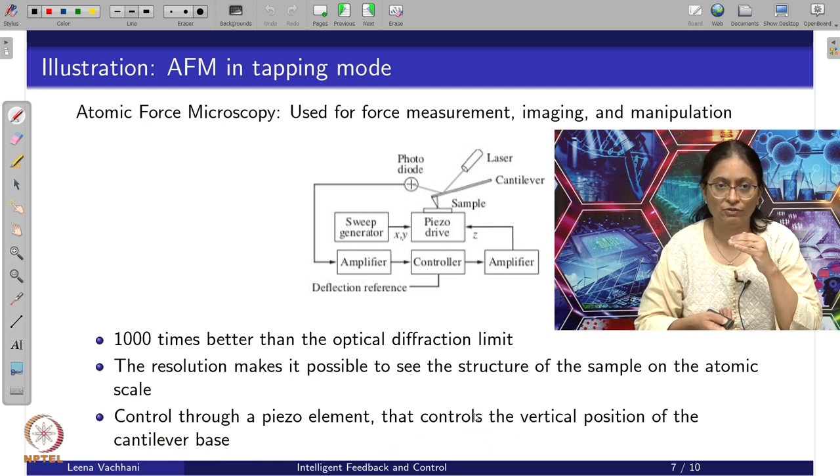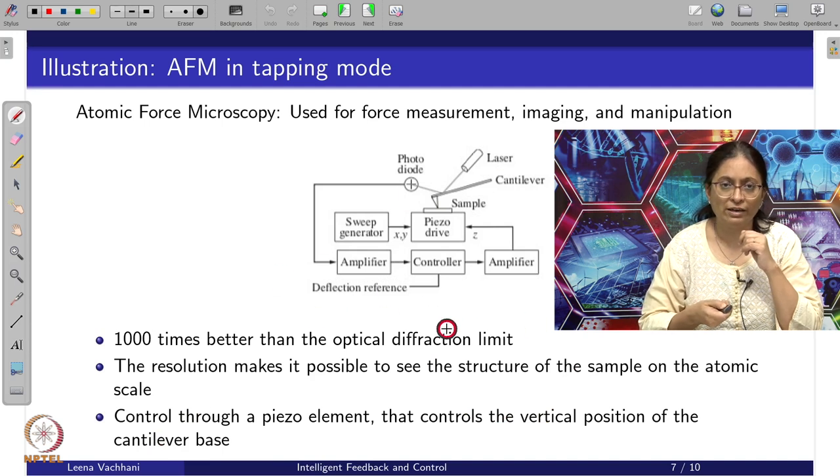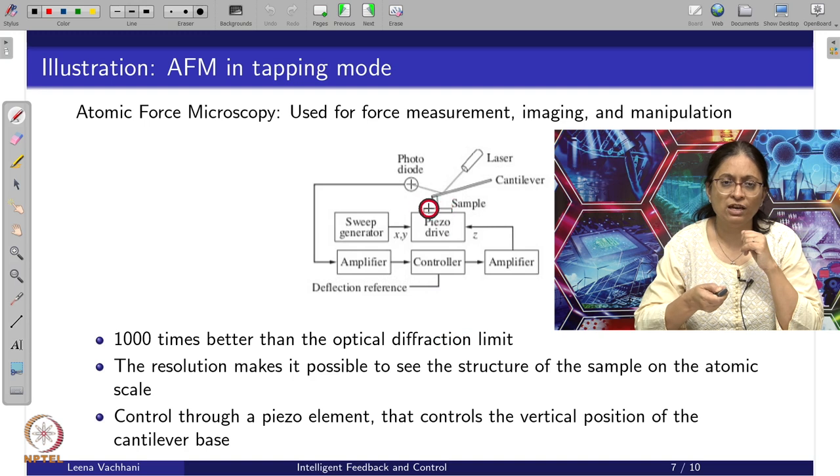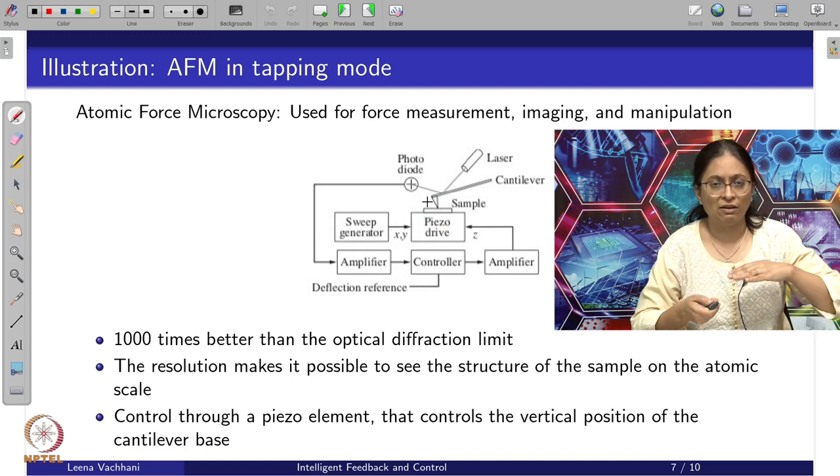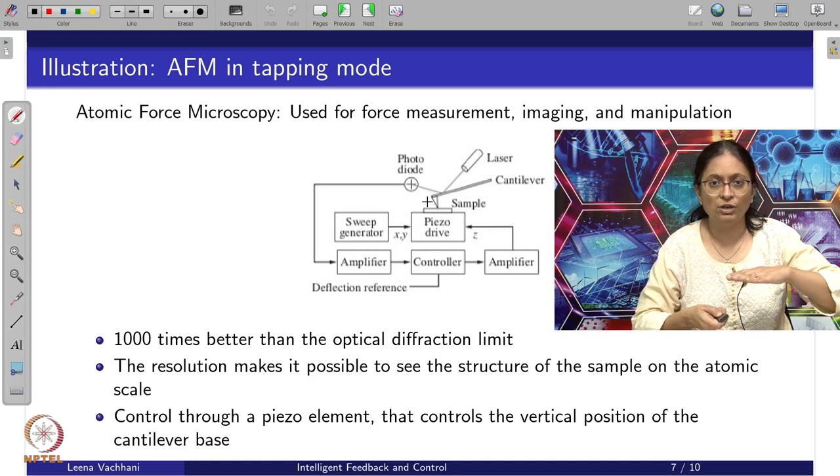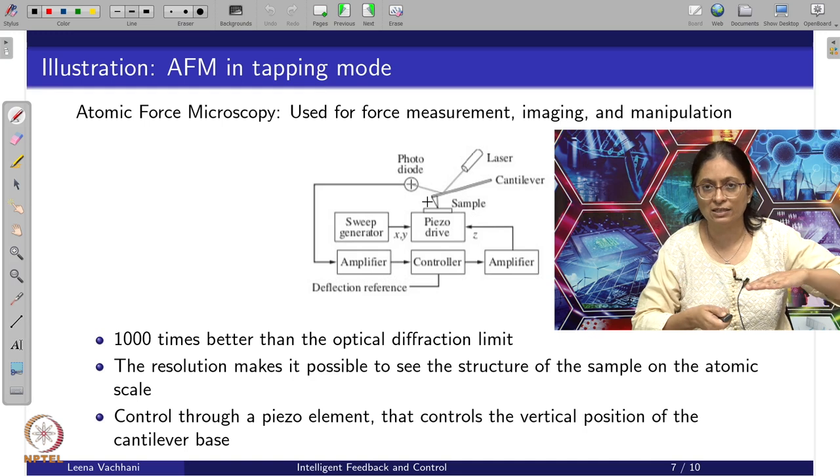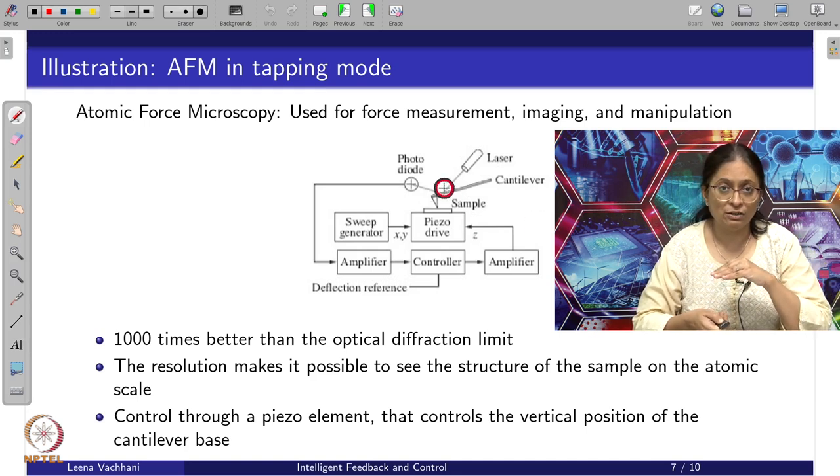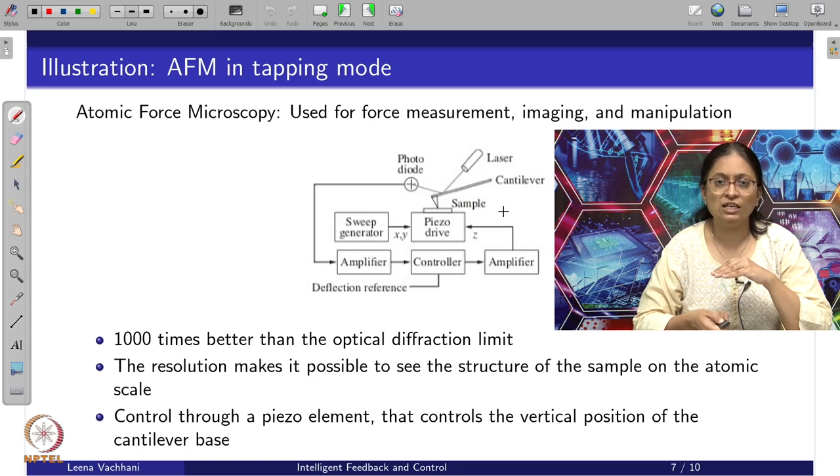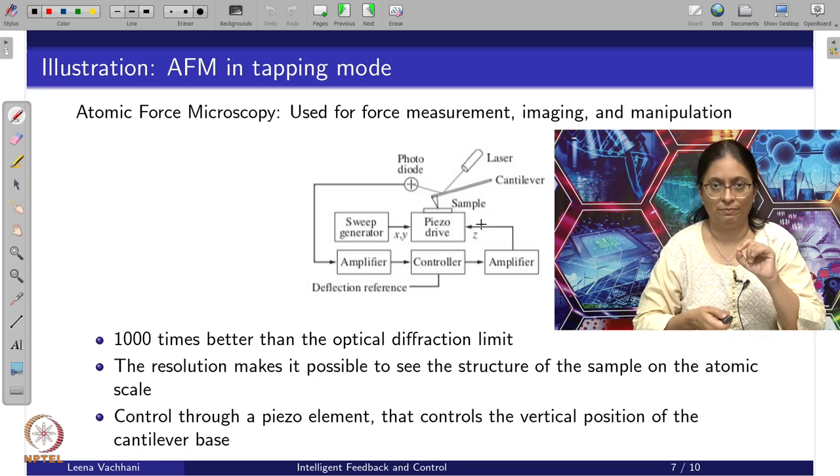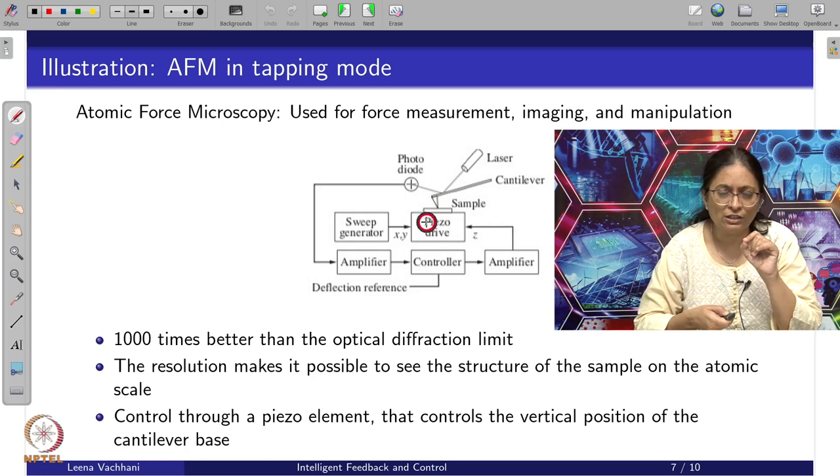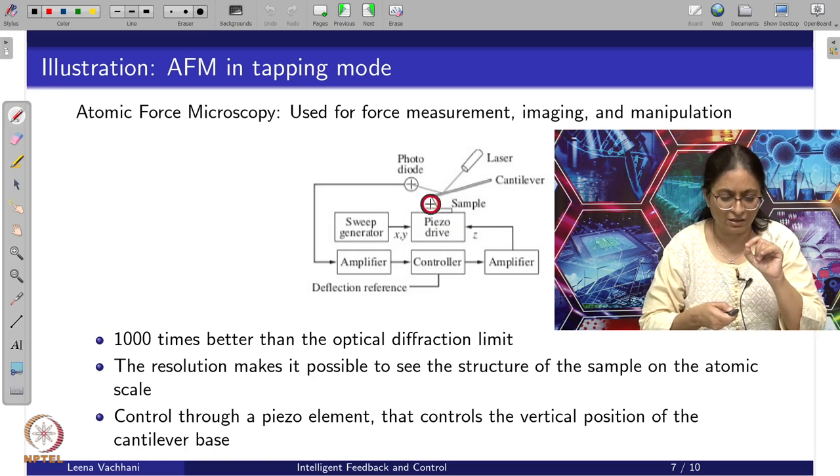This uses control through a piezo element that controls the vertical position of the cantilever beam. Let's understand this through this diagram. Your sample is placed on the piezo drive. This piezo drive is driven by a sweep generator which is moving this sample in x and y directions. At the same time, there is a controller which is changing the z position of the piezo drive depending upon what the sample depth is at an atomic level. How is that measured? There is a cantilever sitting here, which has a tip at the sample. If there is a deviation in the depth, then this cantilever shifts and the photodiode or laser and photodiode captures that deviation.